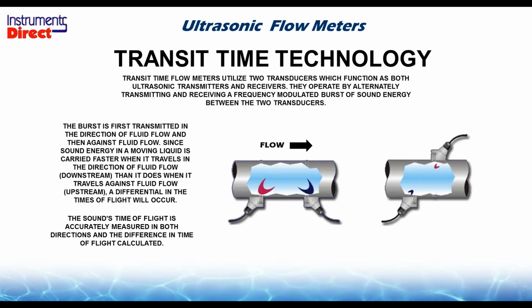The differential between the transit times is what we use to derive how fast the volumetric flow is moving through that pipe. The faster the flow rate, the faster the sound beam gets carried downstream, and the longer it takes to come up against that current. So the differential is what we use to measure flow, and we do it most accurately. Transit time, do not confuse it with ultrasonic Doppler. Ultrasonic Doppler sends a sound beam in and it bounces off suspended particles. If you don't have any suspended particles, an ultrasonic Doppler flow meter will not work. So for the most part, you will not see Doppler flow meters in HVAC, water, or irrigation, because it's too clean for the technology to work.